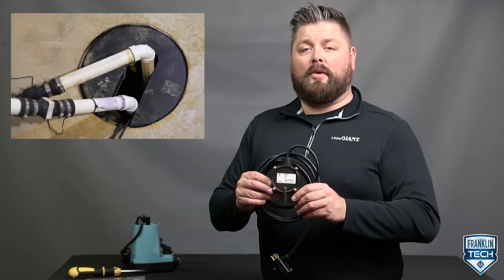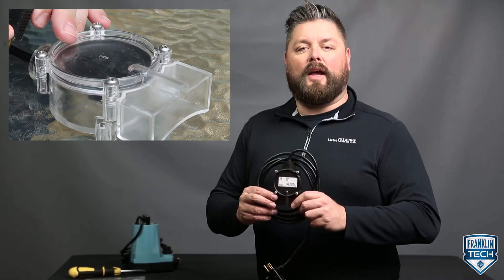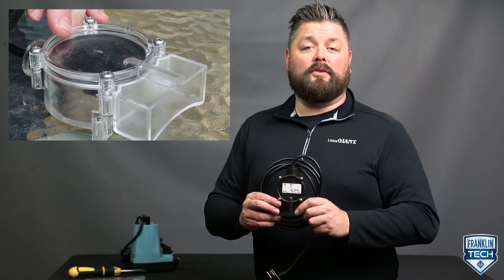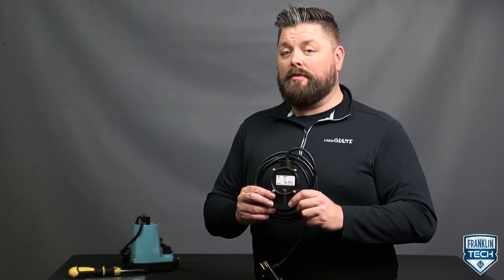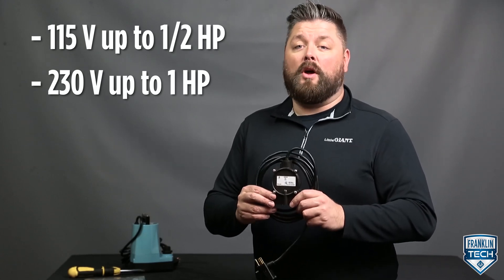With a small footprint, this switch can be used in compact sump pits or bases. Reliable and versatile, this switch is self-contained with no moving parts, and can be used for pumps with a 115 volt option up to 1/2 horsepower, and with a 230 volt option up to 1 horsepower.